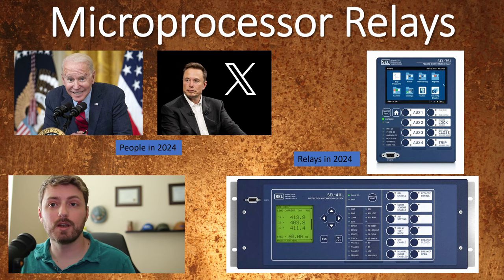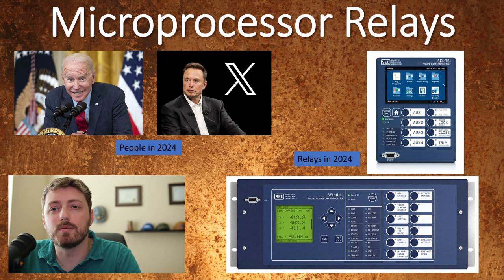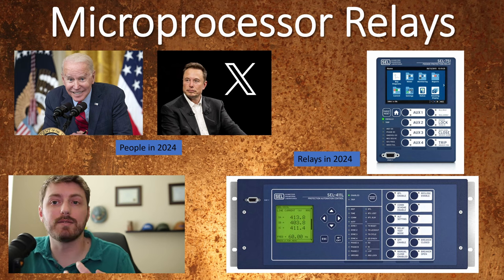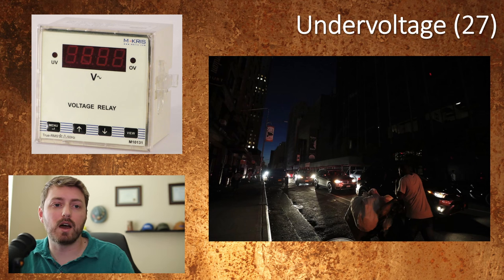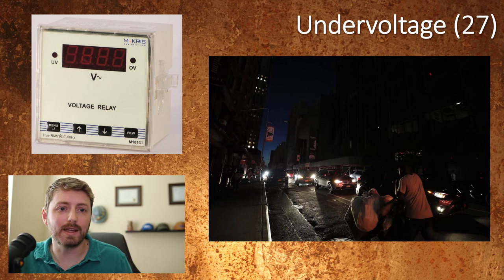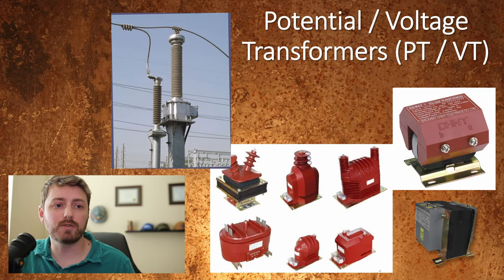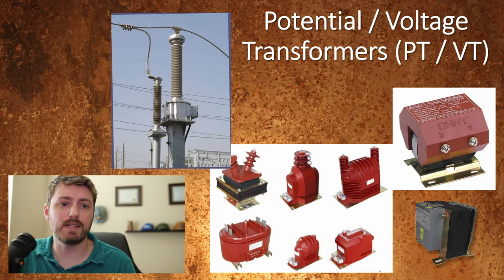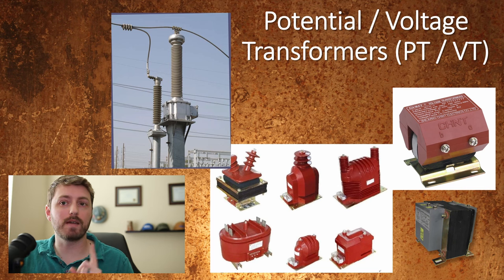We've been talking about overcurrent and thermal protection up to this point because that's probably 80 to 90 percent of the circuit protection out there in the world. But what if you need to safely shut off a system whenever the power goes out, or you have sensitive equipment that'll catch fire if the voltage dips too low? Certain applications like elevators and automatic transfer switches need to detect under-voltage conditions, so we use the aptly named under-voltage relay. Similar to how CTs are used to get proportional current from a power circuit, small transformers called VTs or PTs are used in the same way to get a safe voltage signal — usually between 60 and 120 volts — down to the protection relay for measuring.